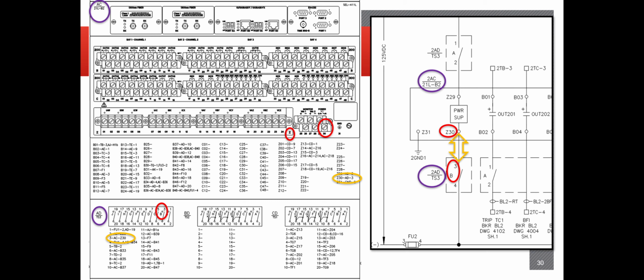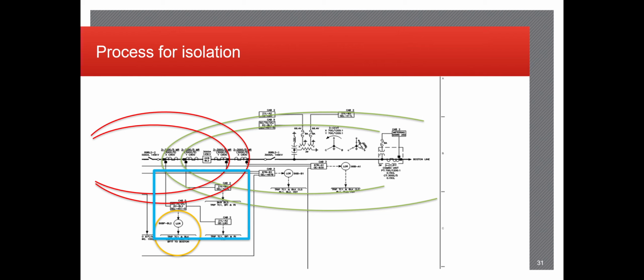You also want to identify in the wiring diagram that the naming conventions are correct, depending on which piece of equipment you're looking at. So we're going to go over a quick little process for the isolation procedures. Again, we're going to be looking at our zones of protection, identifying what equipment is going to be necessary for the isolation, etc.